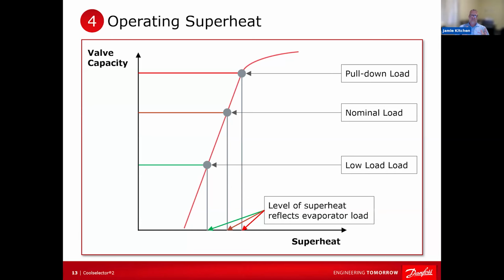And the idea is that the most accurate part of the stroke for this TXV is between pretty much zero and nominal load, right? And the nominal load is what the TXV is rated for. So if you buy a 1-ton TXV, that is your nominal load. What most people don't realize is TXVs will give you 20, 30, 40% more capacity than what they're rated at. But you see how that line bends over at the top? That means that the superheat opening relationship of the valve, superheat capacity, is no longer that accurate. It's not linear anymore. And so you're going to start to see your superheat rapidly increase compared to the amount the valve opens up. But we can call that a pull down load if you want.